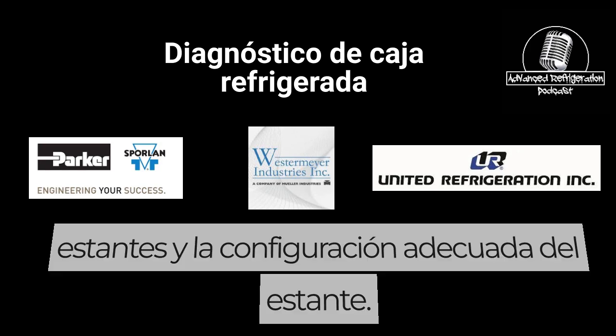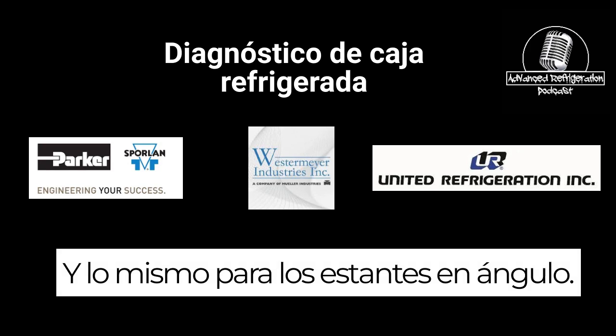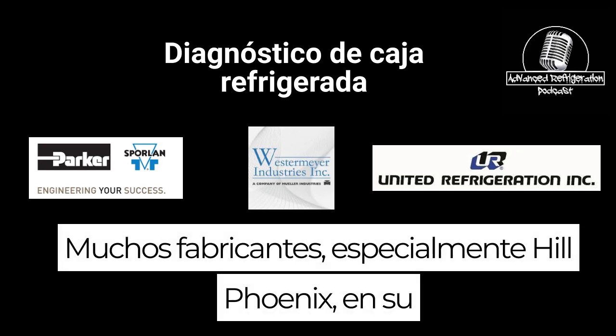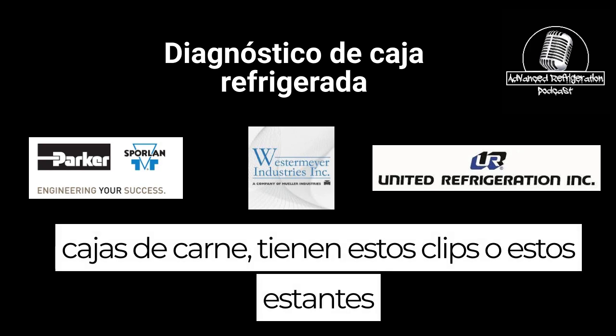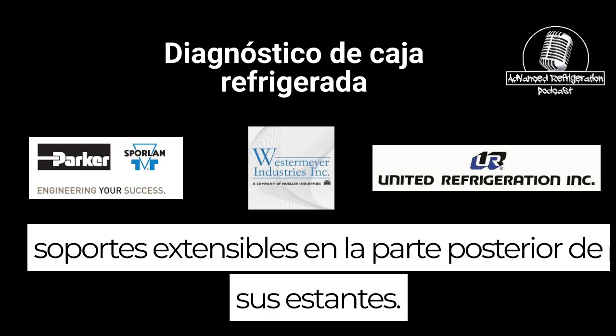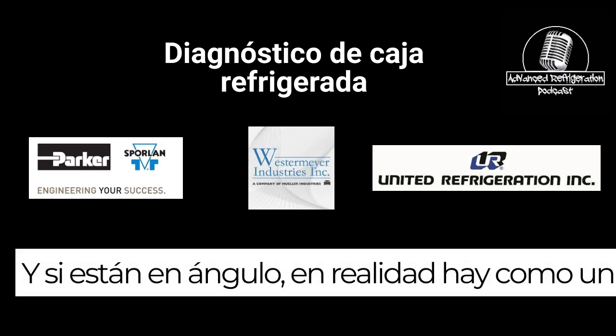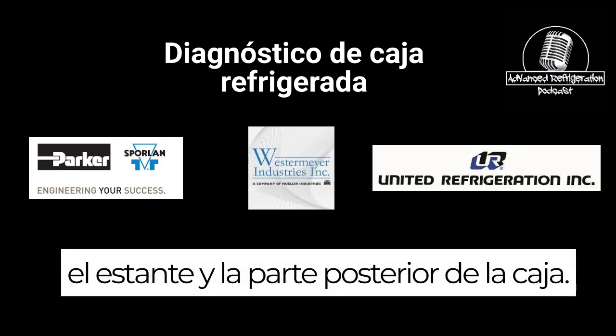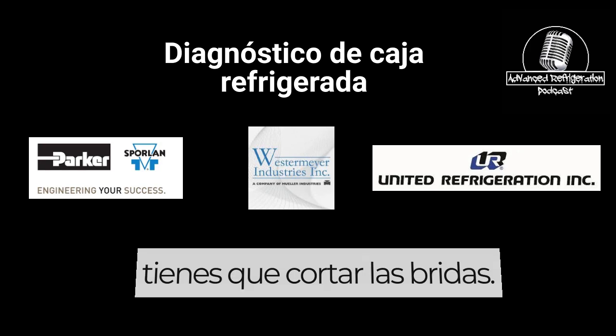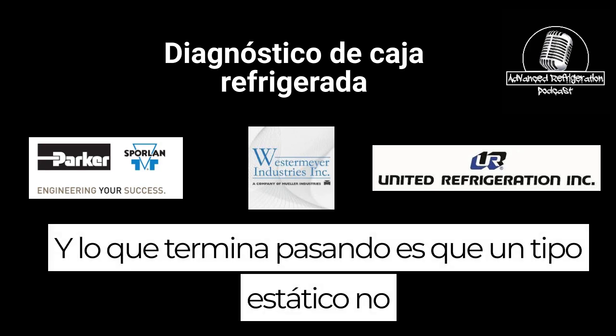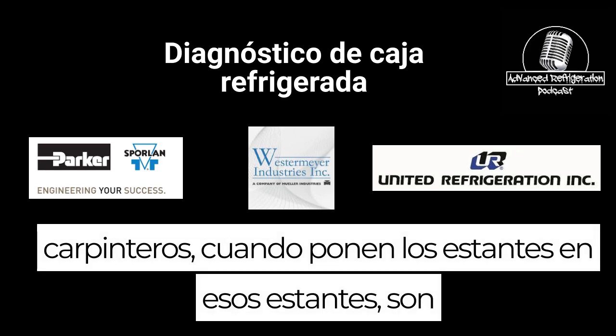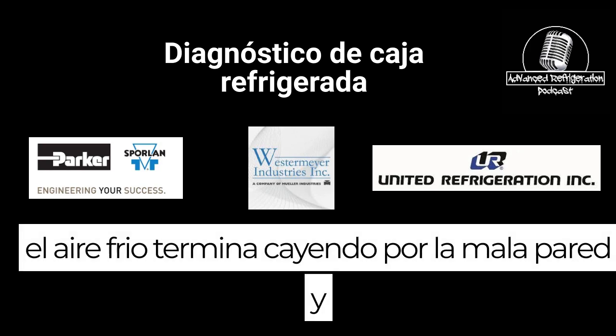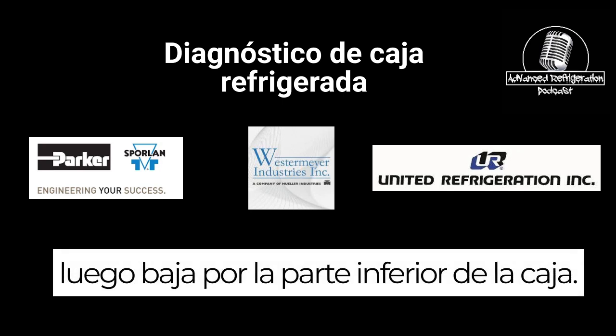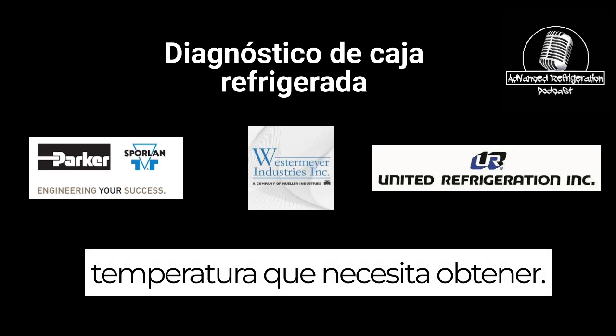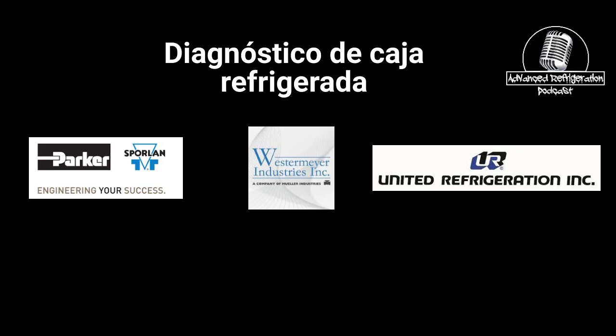So make sure you have the proper shelves and a proper shelf setup. And the same thing goes for angled shelves. A lot of manufacturers, especially Hill Phoenix on their meat cases, have these clips or shelf extending brackets on the back of their shelves. If they're on an angle, there's actually a 2.5-inch gap between the back of the shelf and the back of the case. And there are these spring loaded L brackets that you have to cut zip ties off of. What ends up happening is the standard guy, or the carpenters when they put the shelves in, doesn't go around and cut all those zip ties. Those shelves are going to have a 2-inch gap, and that cold air ends up falling down the back wall and then down to the bottom of the case. And then you don't get the shelf temperature that you need. So that's one thing to be mindful of when you're looking at stuff.